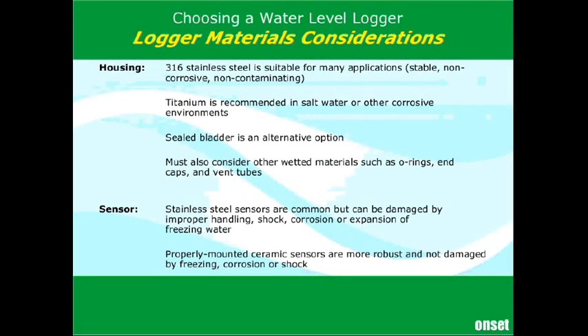In the reverse form, chemical interference, 316 stainless steel and ceramic usually does not release any chemicals that would affect you. Oftentimes there's plastic caps involved. The only way to know for sure is to take a logger and place it in water and do a chemical analysis in fresh deionized water to see what kinds of chemicals are emitted from the logger. One can have contamination from potentially O-ring lubrication that might be used in the logger, so actually testing is probably required. For the frozen logger, the sensor mounting should preclude excessive expansion of ice pushing on the diaphragm. That's really a design issue.